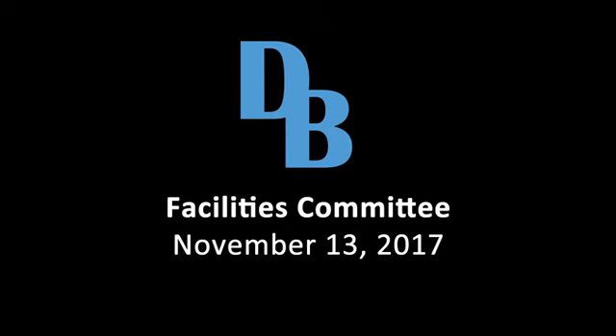And then there's another 9 makeup air units and rooftop units that handle other spaces on the roof of the high school. They're all 20 years old. They're all starting to have some failures of equipment. So we're going to look at what we can do to possibly change the way we use them, to not have to spend a lot of money to condition a lot of air we don't need.